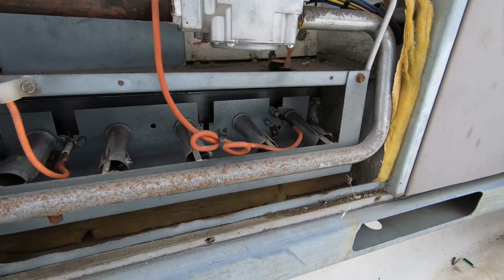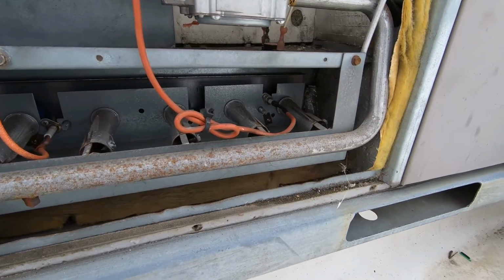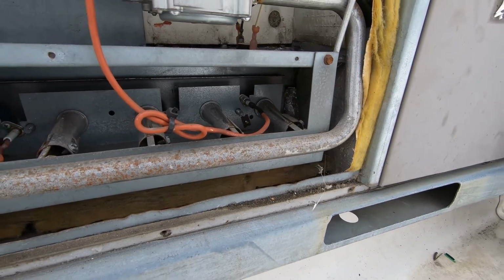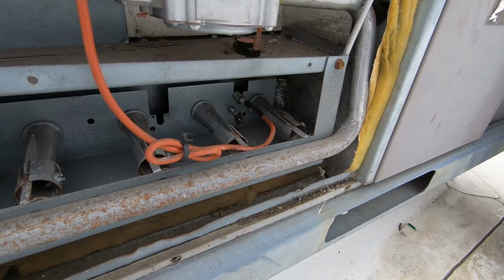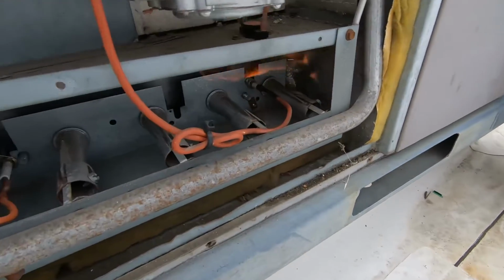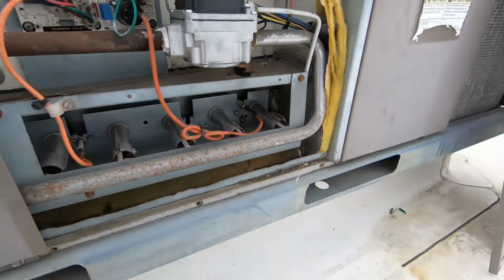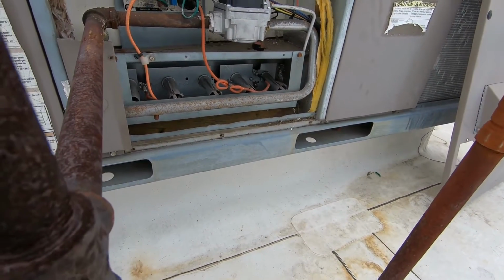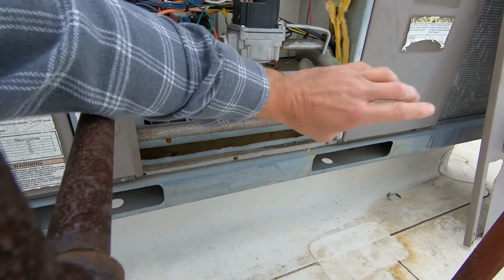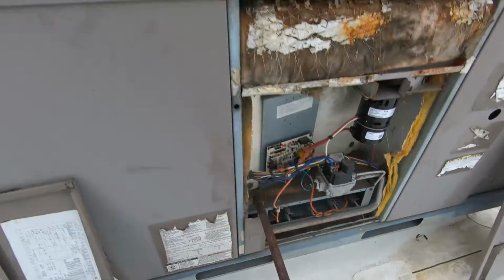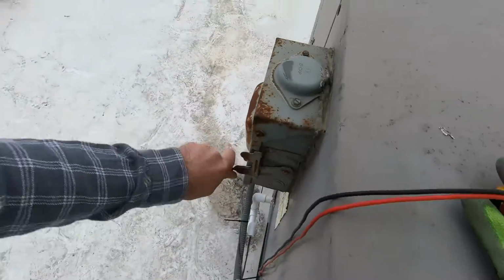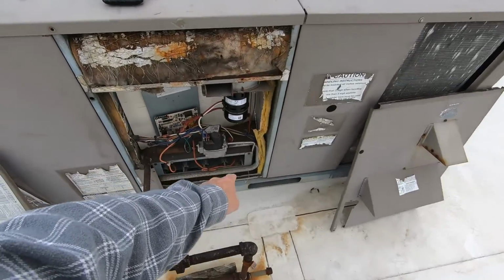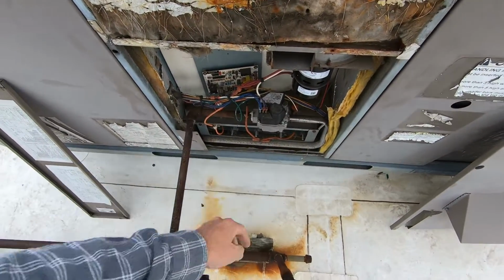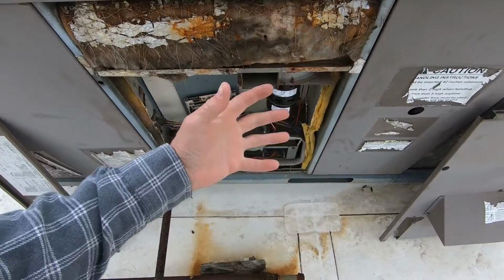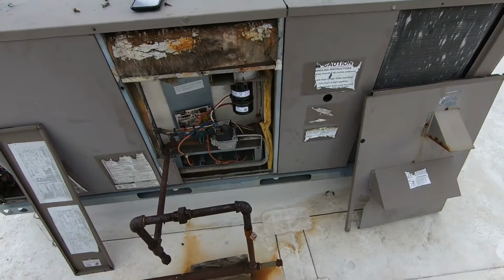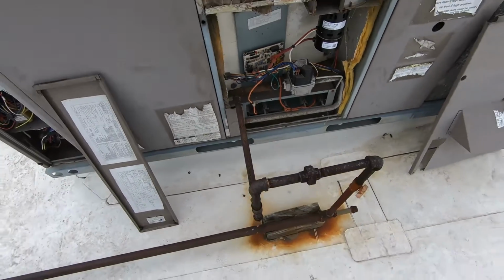All right, so our carryover tube lit, then we lit our main burners. See that? All right, that rollout switch is doing exactly what it's supposed to do. That flame rolled out, heated up this rollout switch, and it opened and shut the gas valve off immediately. I'm guessing we have something plugging up that burner or plugging up this orifice, and it's not allowing it to ignite, and then the gas is building up, and the other burners are then igniting that gas and it's rolling out. So let me go get some pipe wrenches.